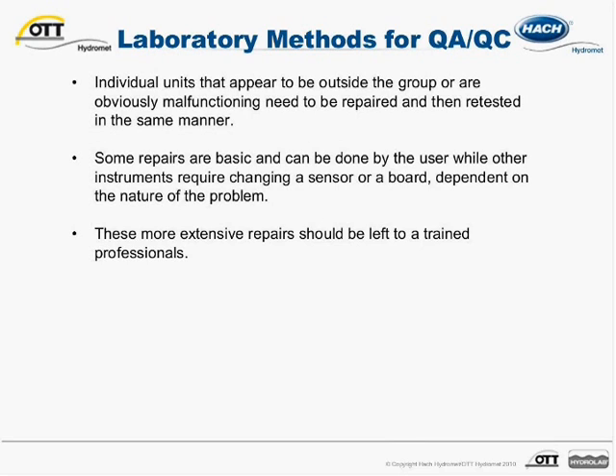It may be that the sensor or setup needs some basic repair that can be done by the user. More advanced repairs will need to be done by a trained service person, possibly affiliated with the manufacturer. Remember that calibration only changes what the sensor reads and will not necessarily fix a problem with the sensor. Maintenance or repair, on the other hand, will change how the sensor measures.